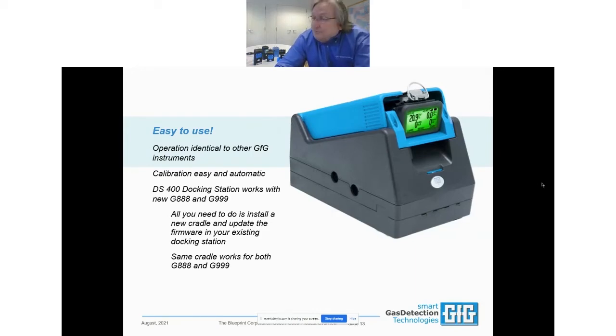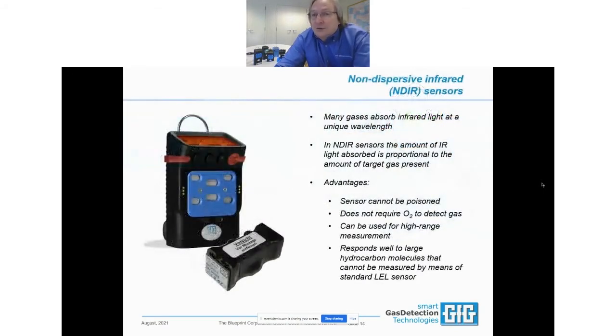The docking station, no difference. It's the same DS400 and DS404 docking stations that you're used to. In order to use an existing docking station with the new products, if it's an older docking station, you may need to send it back to the factory for a hardware update. If it's a more recently purchased docking station, the only thing that you have to do is change the cradle, which is held in place by a single screw and which is really, really easy to do.